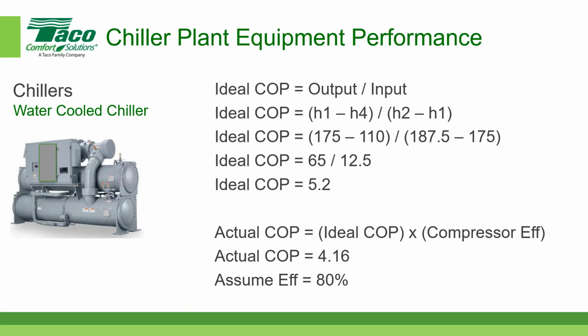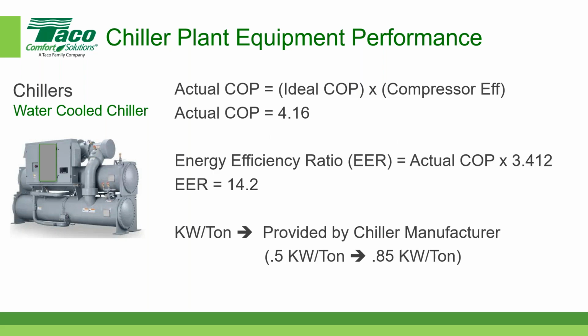So the whole idea of this first part was to get everybody oriented to the fact that it's the temperatures that are driving the efficiency or the energy consumption. That's probably a better way of looking at it. Any other questions, Brett? Somebody asked, why didn't we use an evaporative condenser instead of a cooling tower? That's kind of open for discussion. As it turns out, an evaporative condenser is kind of a closed-circuit cooling tower in a way. But open cell cooling towers, in terms of what we're talking about today, are the more efficient way of rejecting heat.